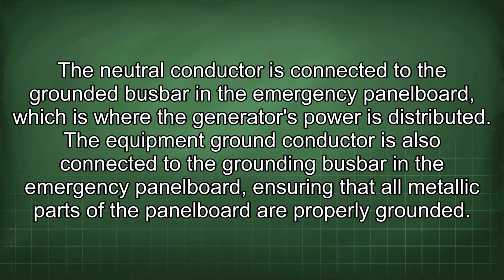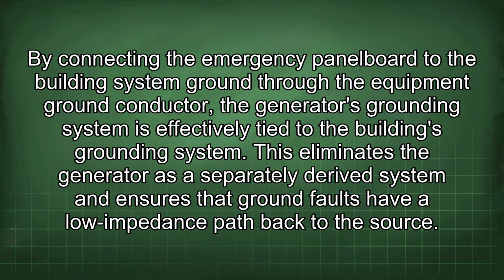The neutral conductor is connected to the grounded busbar in the emergency panel board, which is where the generator's power is distributed. The equipment ground conductor is also connected to the grounding busbar in the emergency panel board, ensuring that all metallic parts of the panel board are properly grounded. By connecting the emergency panel board to the building system ground through the equipment ground conductor, the generator's grounding system is effectively tied to the building's grounding system. This eliminates the generator as a separately derived system and ensures that ground faults have a low impedance path back to the source.